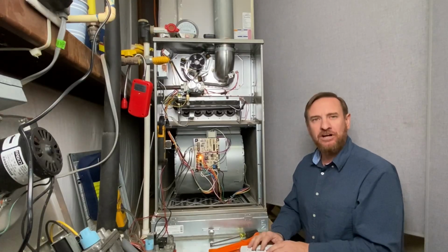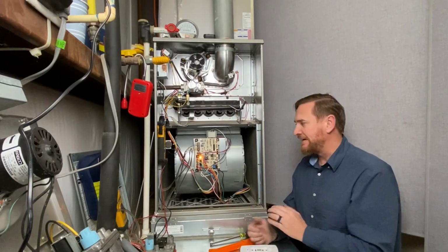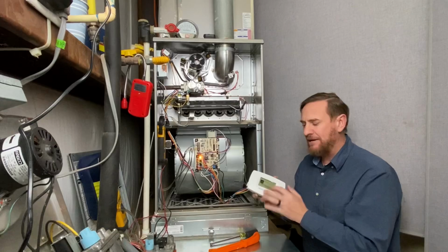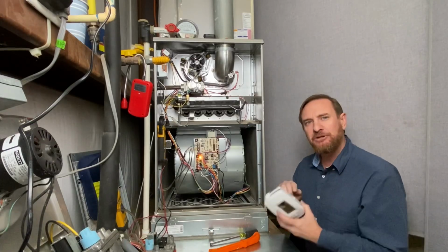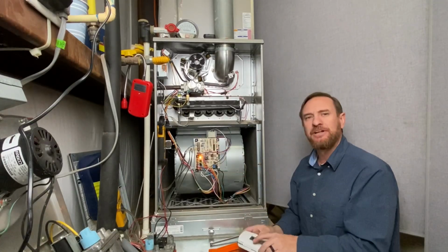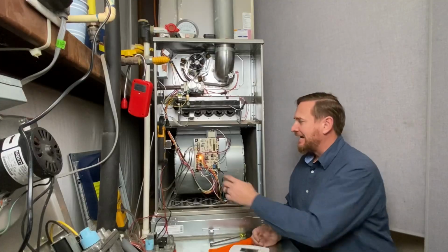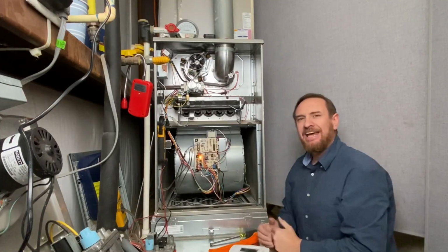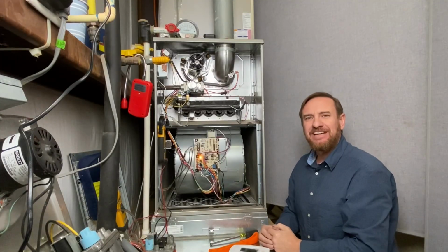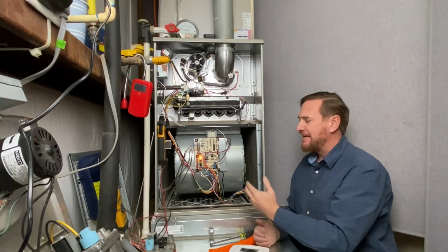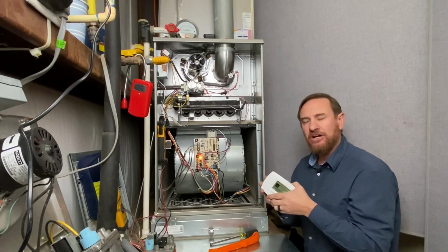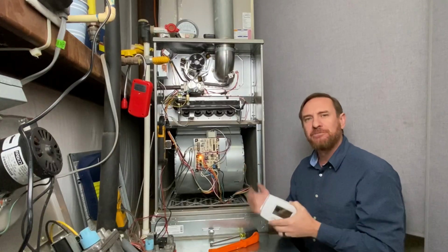Is the thermostat calling for heat? Or is it satisfied? Now remember, it's not just a thermostat. These 24 volts from the W wire have to get all the way back to the control board. This is where a meter comes in handy. I can check between R and W and see I should have 0 volts if it's calling. If I'm reading 24 volts, then that means the thermostat's either not calling or the wire's broken somewhere between there.